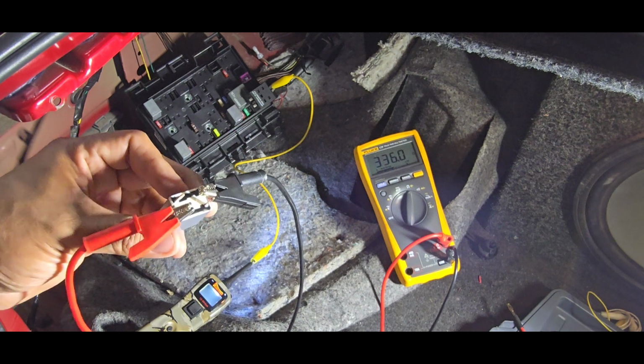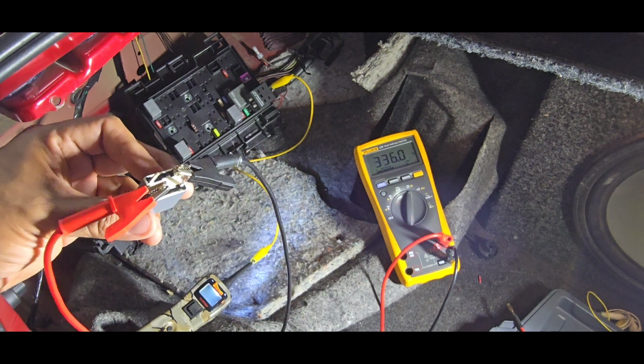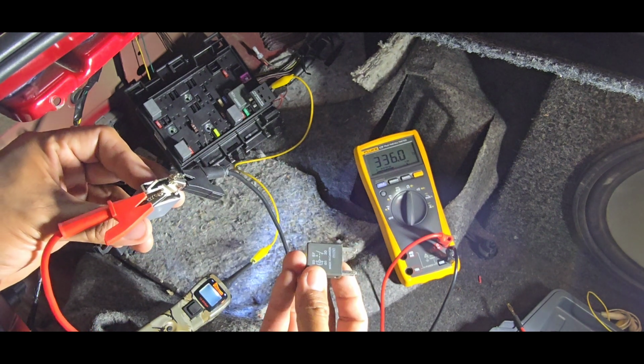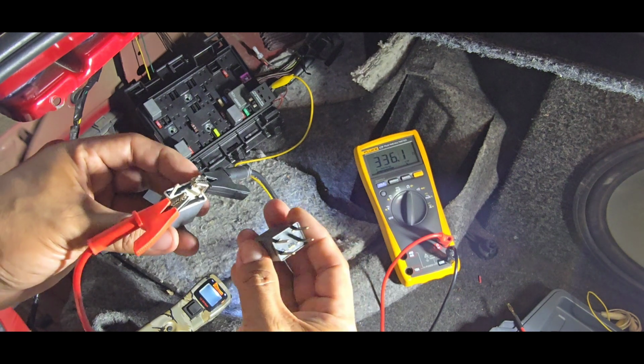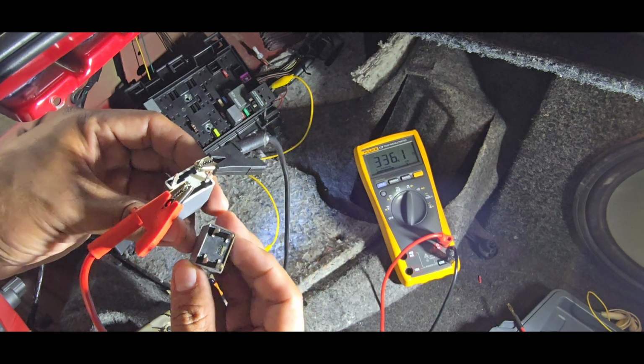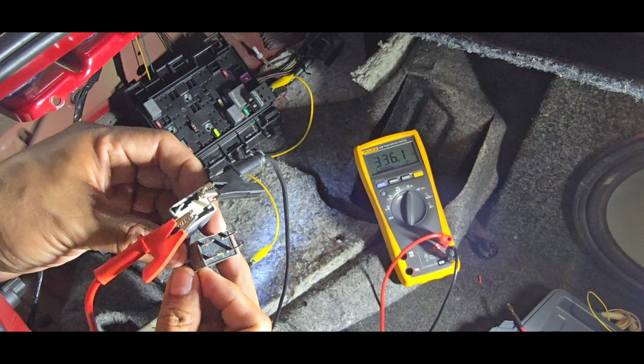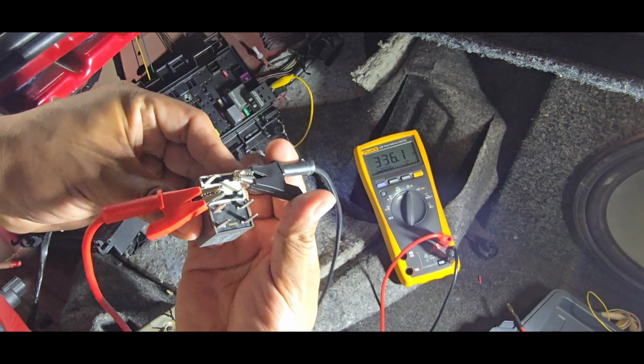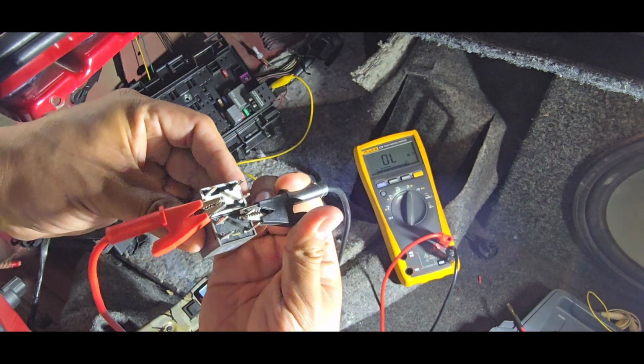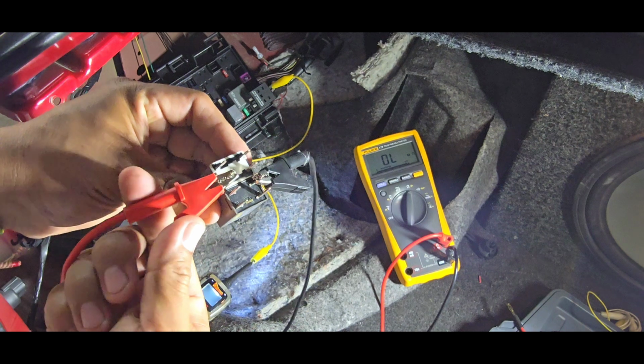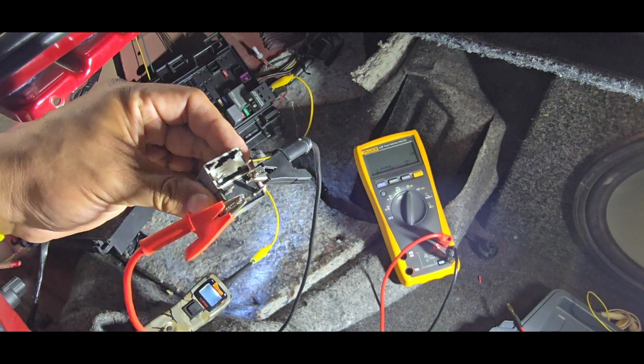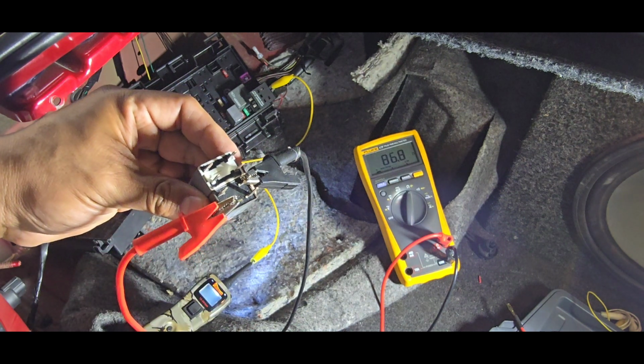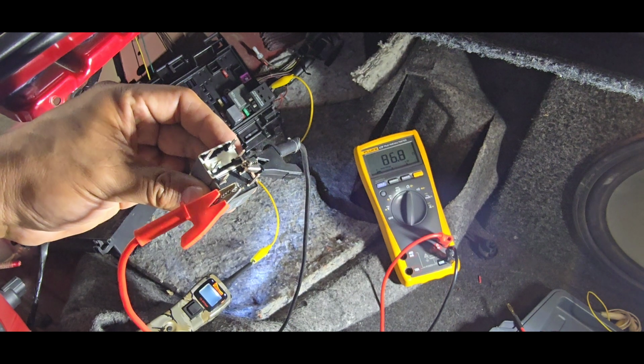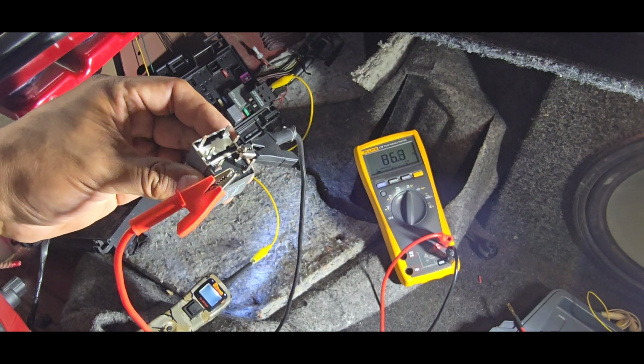Let's switch this to a known good relay. I have another spare relay here, a known good one, and we're going to do the same thing, moving our leads to terminals 86 and 85. Our meter shows 86 ohms, which should be anywhere from 60 to 100 ohms.